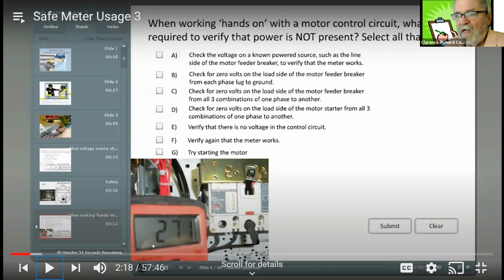So now we're going, I'm on phase B. And if I go over and screw, that's phase C, phase A is on the left. So it's saying check for 0 volts on the load side of the motor feeder breaker from each phase lug to ground. So is that a good thing? Yeah, I'd do that. Okay, we want 0 volts. Yep. Here's C: check for 0 volts on the load side of the motor feeder breaker from all 3 combinations of one phase to another.